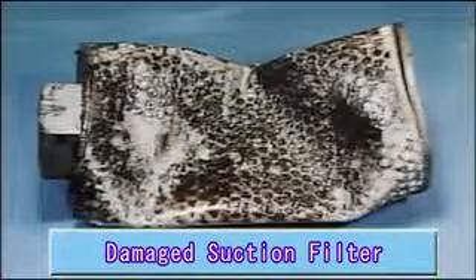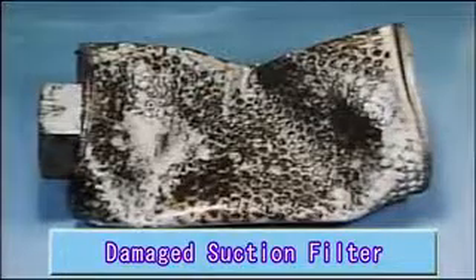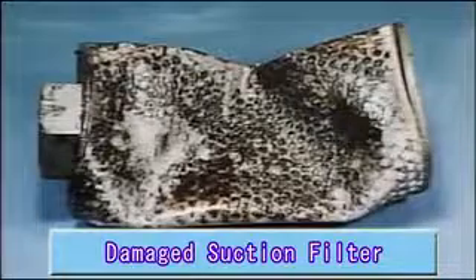Sludge causes blockages which damage filters. This is an expanded photograph of blocked filter mesh and the adhering sludge. Photos show the inside of an oil tank of hydraulic equipment. You can see the contaminant, called sludge, adhering to the inner walls.